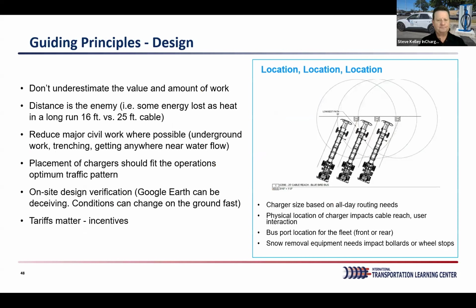Next, when we look at design principles, what is the right cable location? It still amazes me that this is an issue in the industry. They look at cable lengths, say you have a 16-foot cable, measure from the charger to the port, and say it's 16 feet so it'll work fine. But it won't, because there's a bend coming out of the charger, and another bend as it goes over to the charging cable and into the port. So you really need something closer to 12 to 13 feet to make that work.